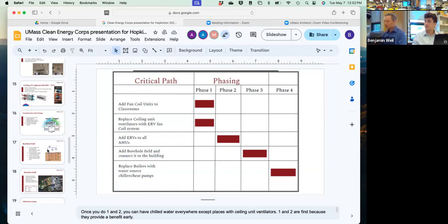It's great, but it's very unusual to find all the conditions necessary to do that kind of a well. The problem with a lot of the open loop systems has mostly been filters. Yep. They become a maintenance nightmare. And so people are tending to not recommend that very much anymore. So it's most likely that you would end up with a closed loop borehole field. And only after drilling a test well would we know how deep it should go. Like what's the ideal depth for this location and how many you really need, right? We've estimated 20 based on the typical production of a 500-foot well from a bunch of Massachusetts locations that we know about. But this is not specific to your location. So the first step really would be a test well.